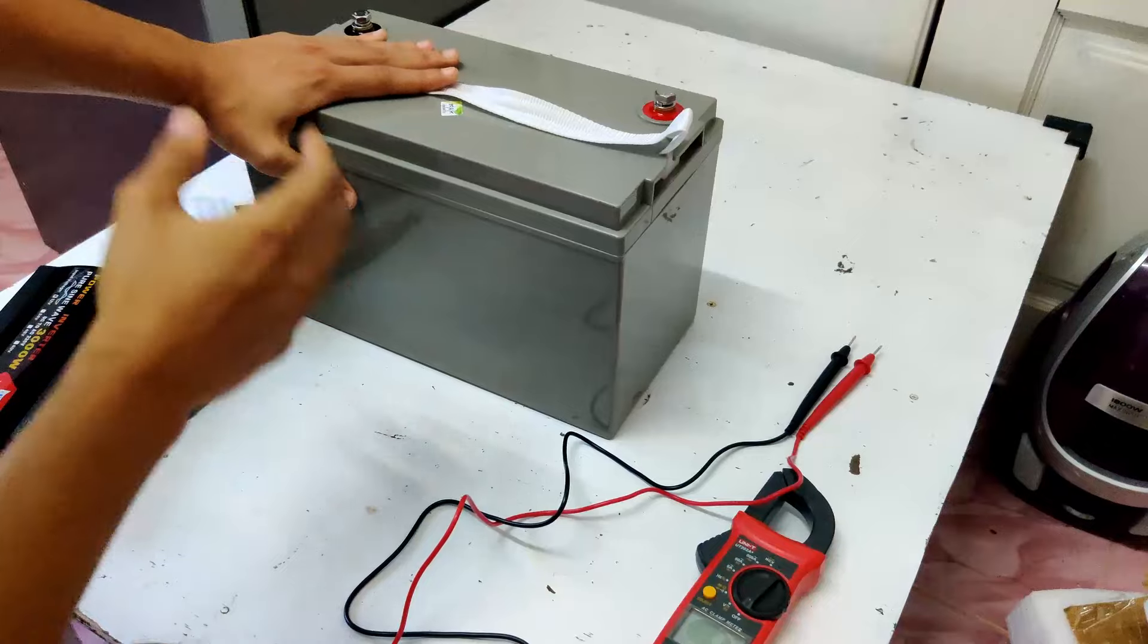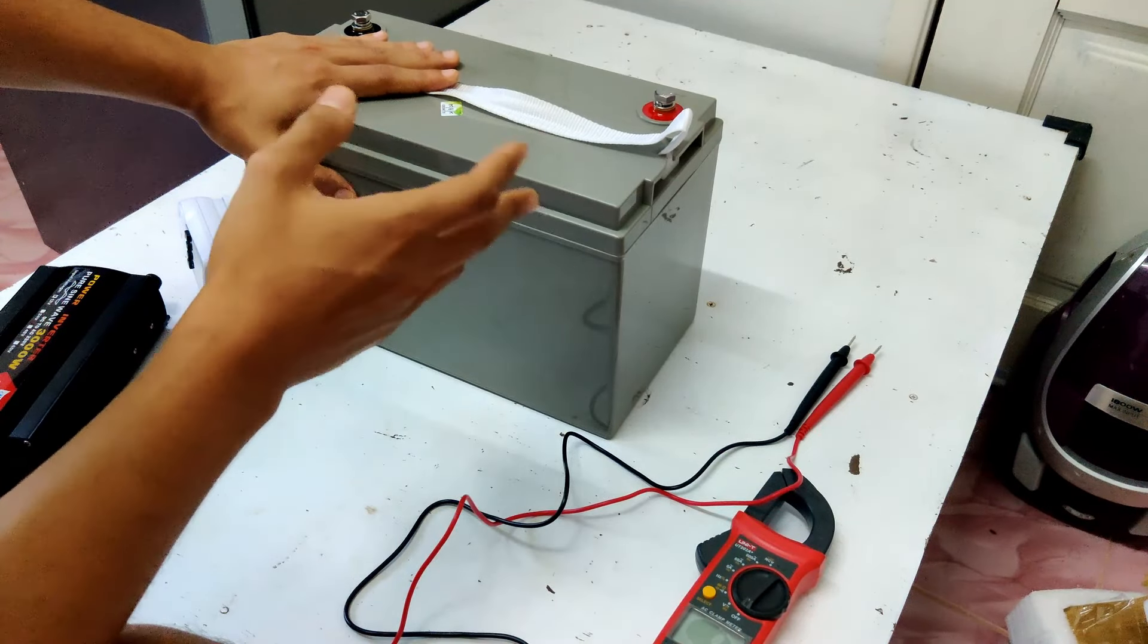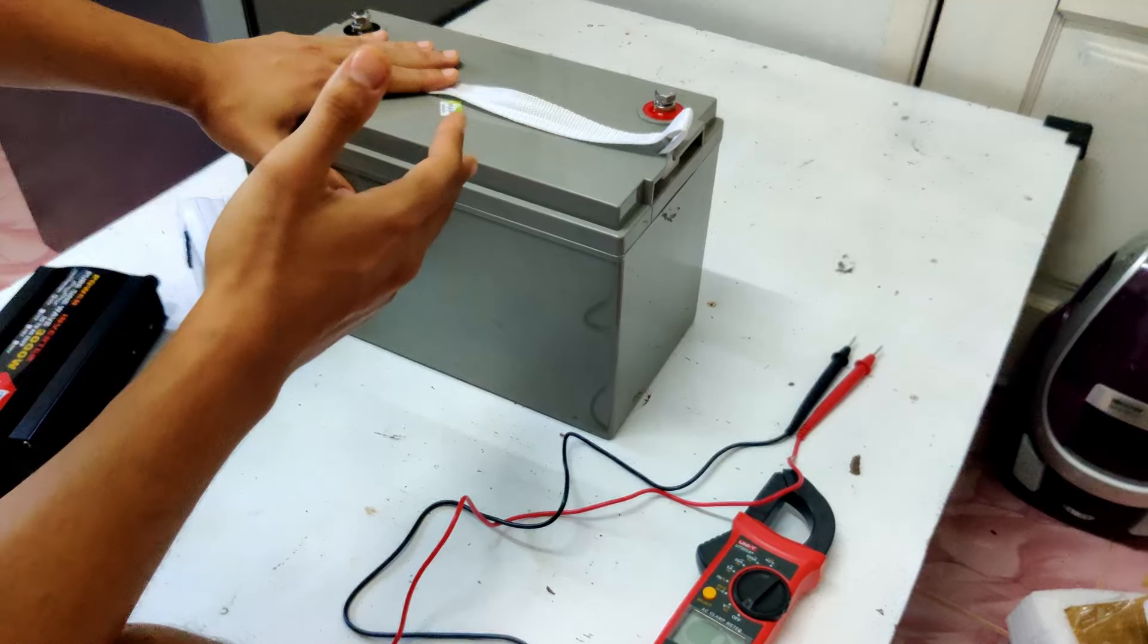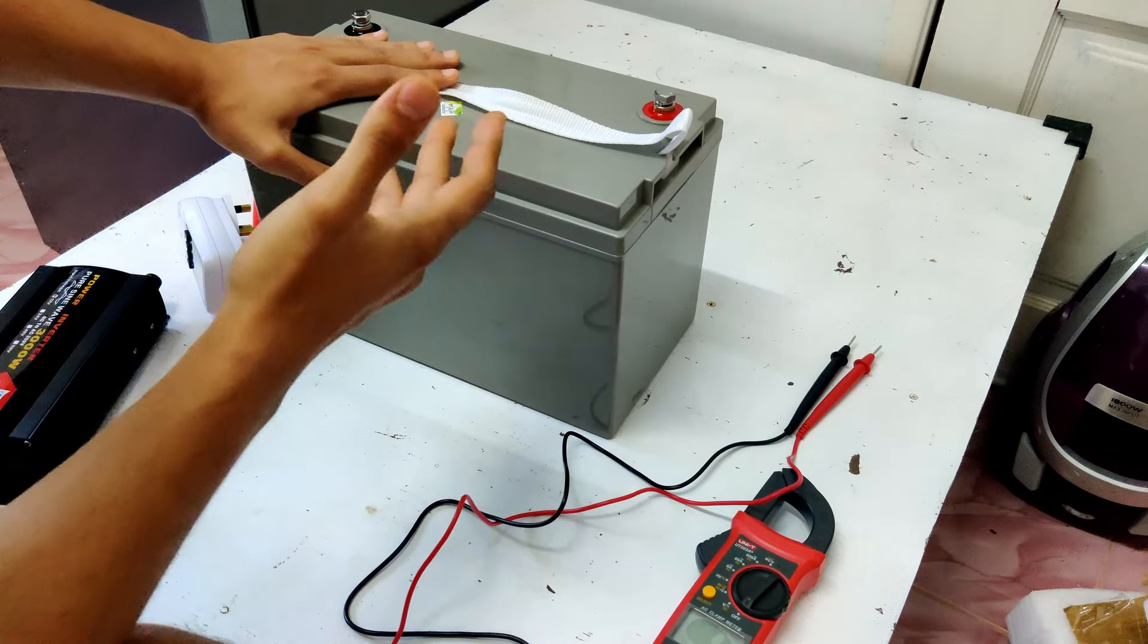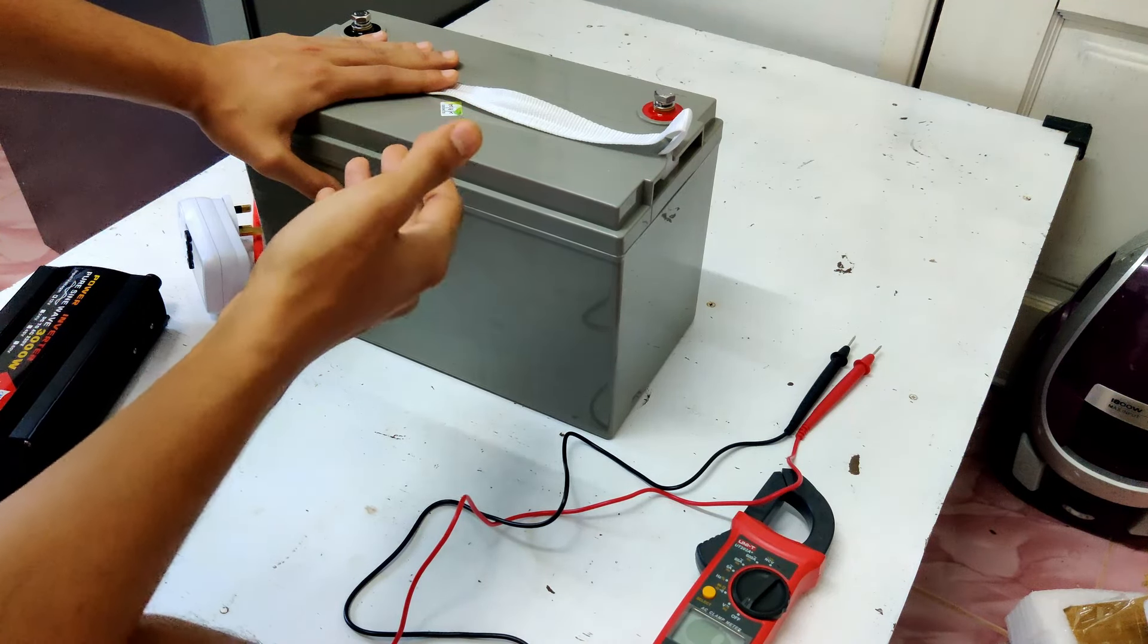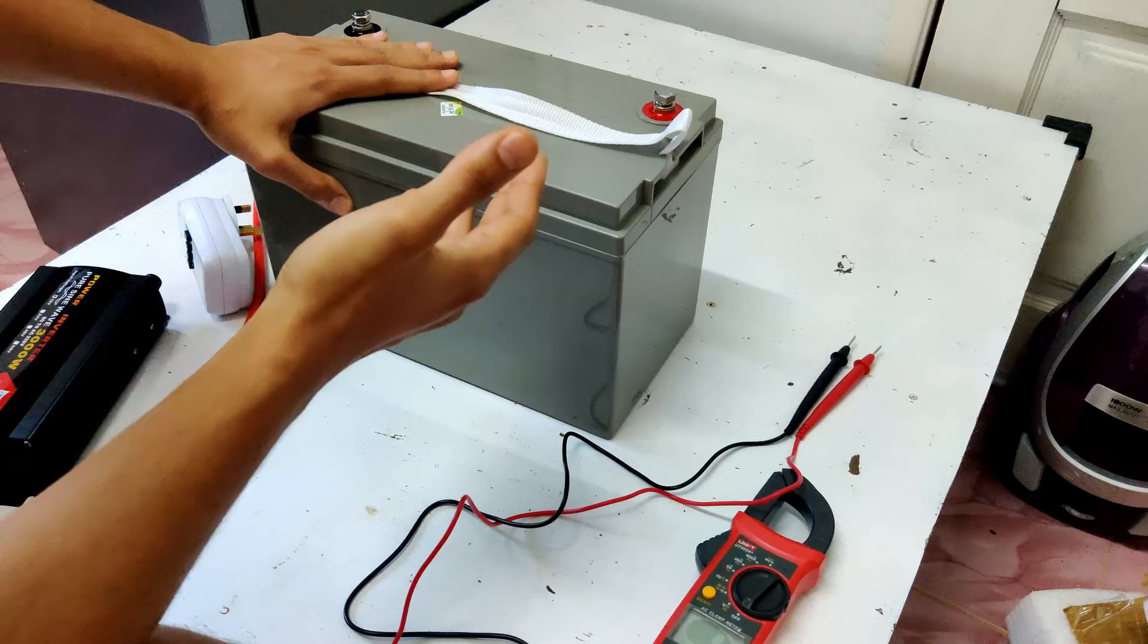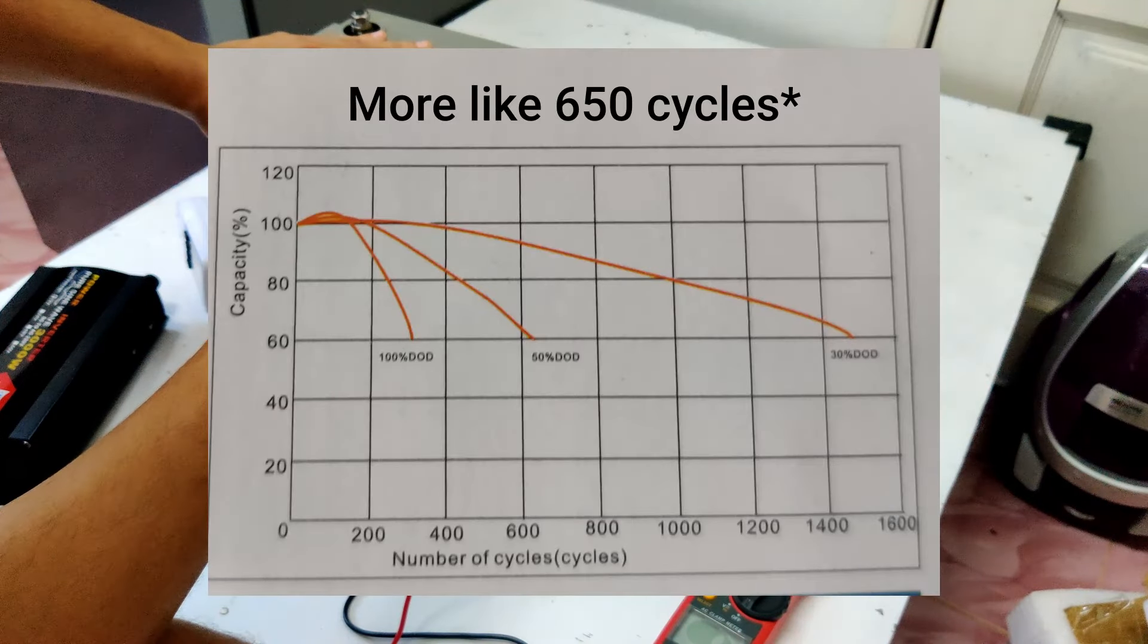Now, the only reason I'm limiting myself to 50% of this battery's capacity is to extend its lifespan, or more precisely, to maximize the charge-discharge cycles that I would get out of it. But if you have a gel battery like this one, of the same size, and you're only using it as an emergency backup for when the power goes down, you don't really have to worry about that, as these are deep-cycle batteries. And even if you repetitively fully discharge them, you could still get 200 to 300 cycles out of these batteries. By limiting myself to only 50% of the battery's capacity, I expect 800 to 900 cycles out of it.